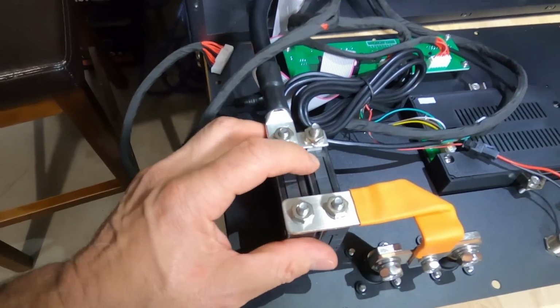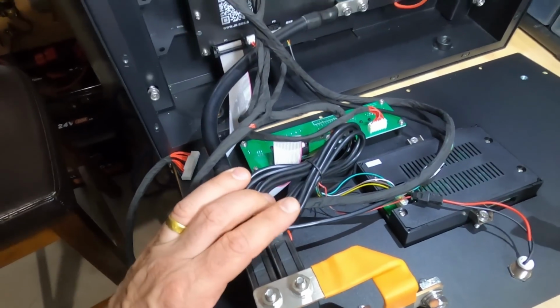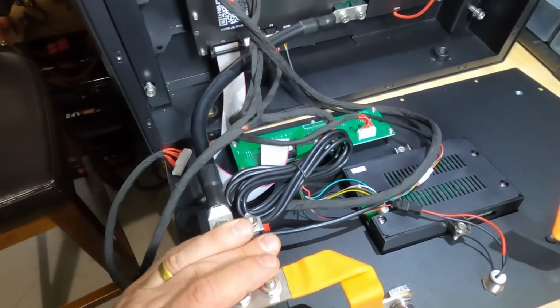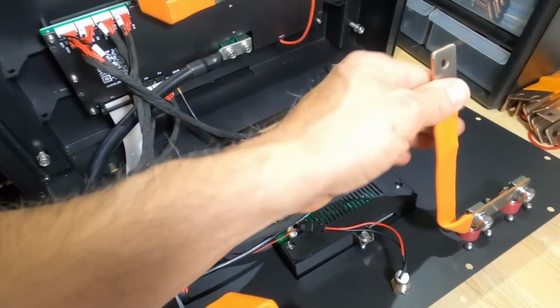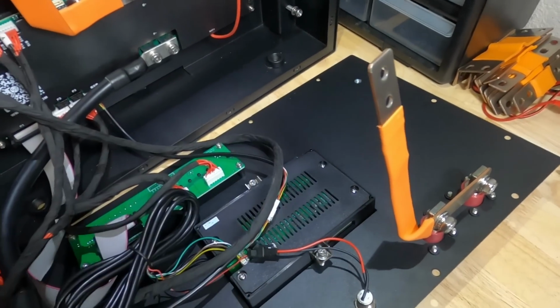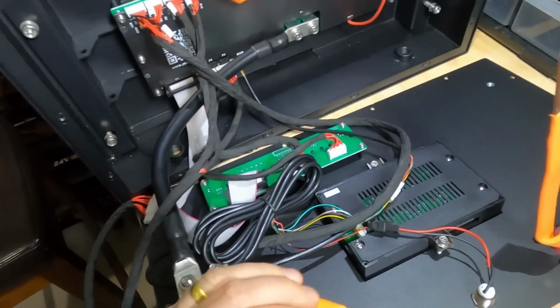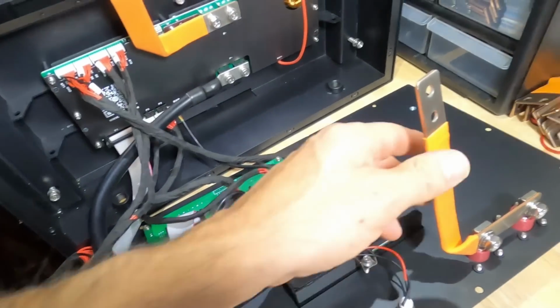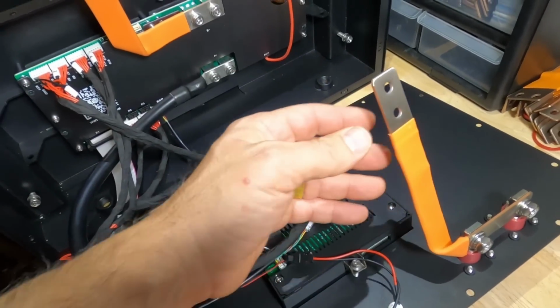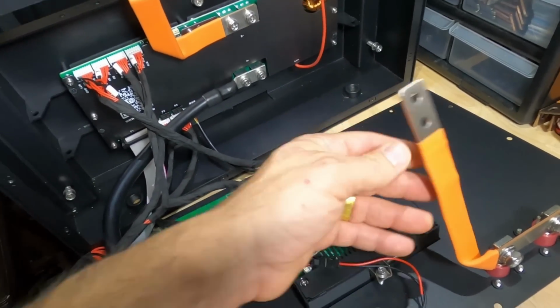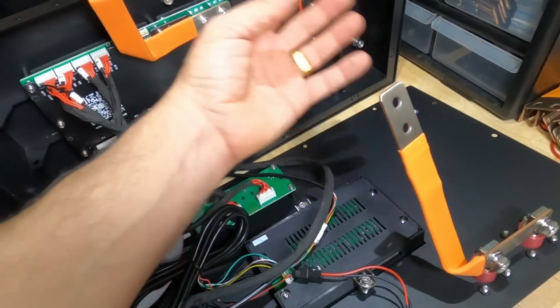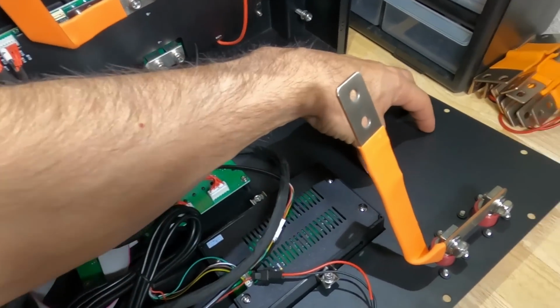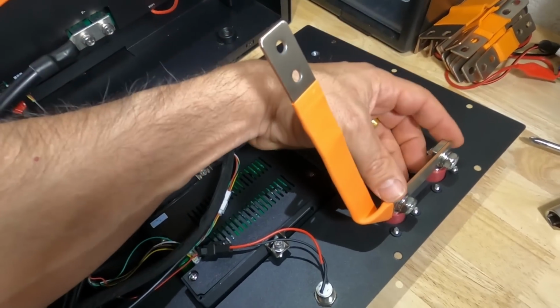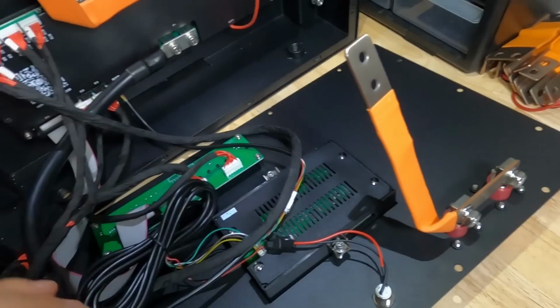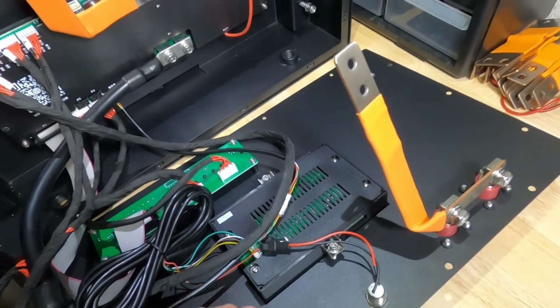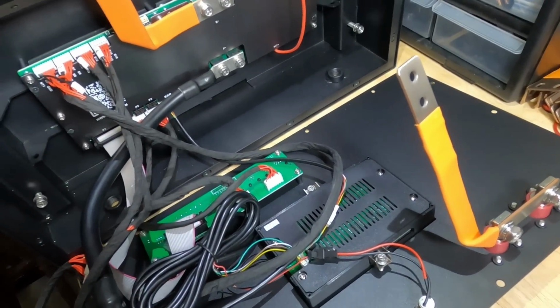They've got the circuit breaker on the negative side of the battery, which is kind of strange. Typically circuit breakers and fuses go on the positive side of the circuit. They said they did it because of wire routing issues, but I don't see any reason they couldn't finagle one of these bus bars to go over here and connect to the breaker. There's tons of space, and then connect it to your positive terminals. I don't know, hopefully they do that in the future, but they said it had no effect.